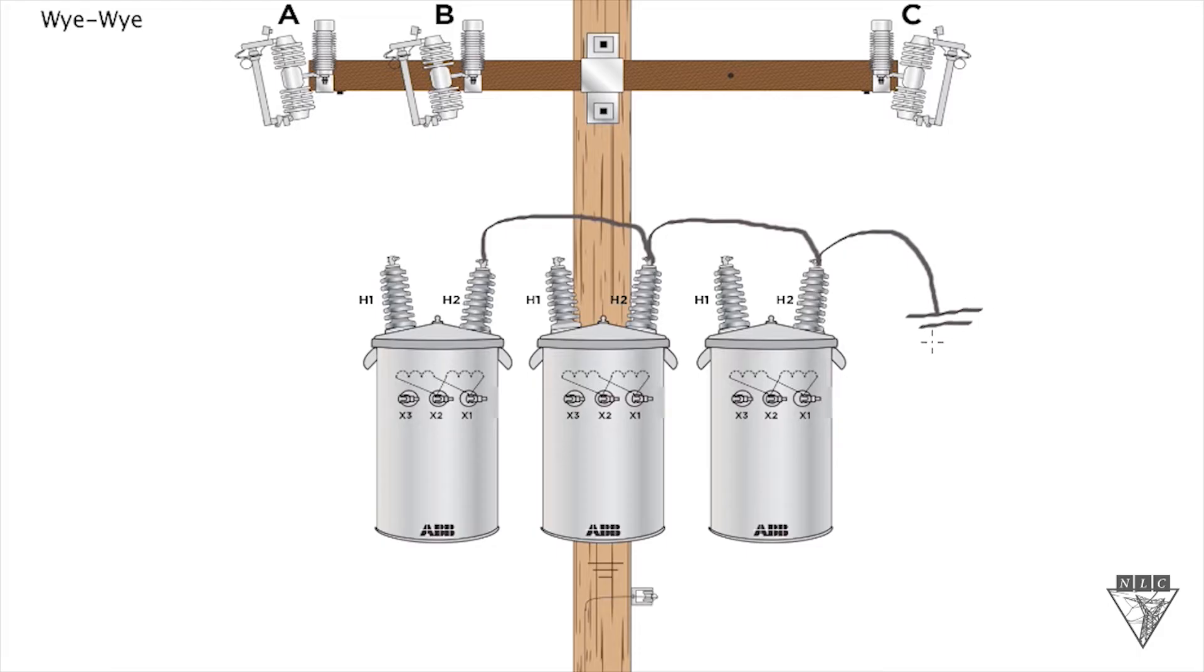A common saying with a YY connection is YY you tie. What this means is we're taking all the H2 bushings and tying them together, then tying that to ground. YY you tie, you're tying the H2 bushings to ground.